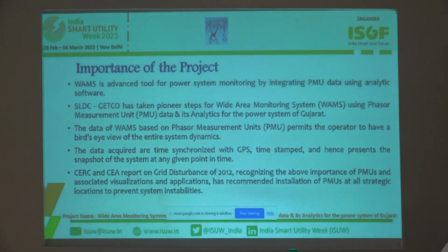At present, all grids run through the SCADA system, which is a redundant, well-placed system used by all utilities, but it has two difficulties. Its data comes after 7 to 10 seconds, so there is latency, and the data becomes historical, not a present screenshot of the system.